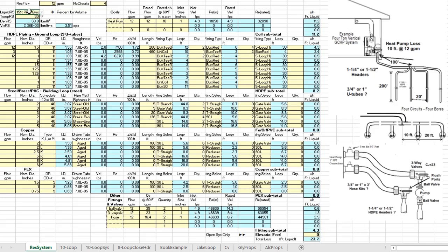Okay, we could also try another antifreeze. I think a lot of people use ethanol, so we could use ethanol and get it down a little bit to 23.8, and we're in good shape. So it's very, very important to conduct this exercise if we're going to make these things efficient. That's our goal, make these things efficient, and the bigger the pumps, the less efficient they are, and so we can improve that by judicious use of this program to reduce pump size. So I encourage you to do your analysis, and I hope this helps you out.